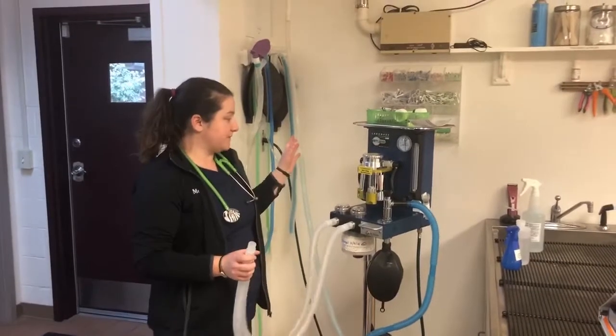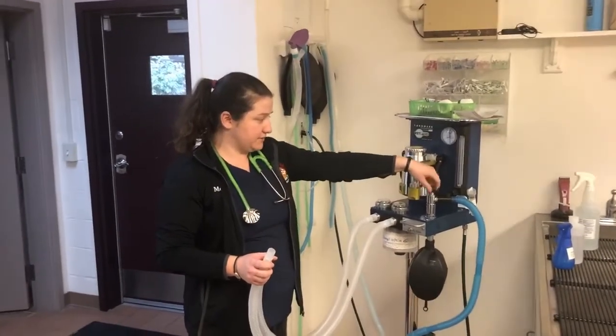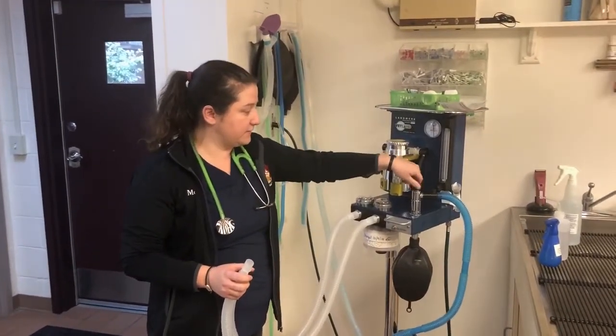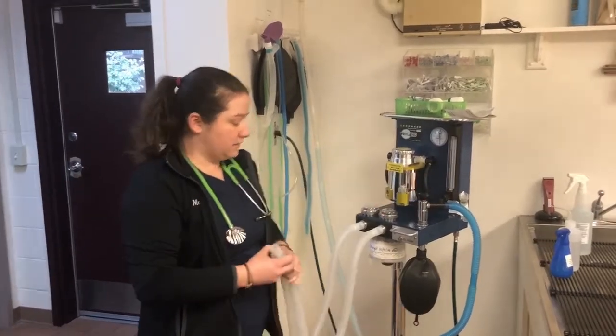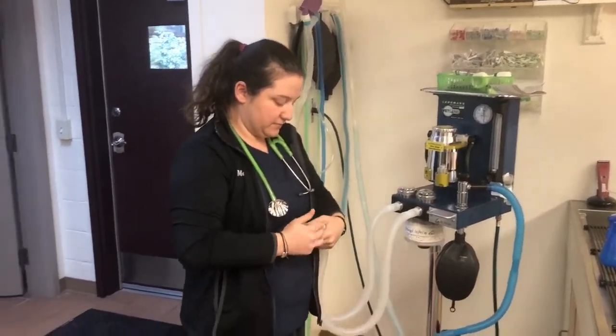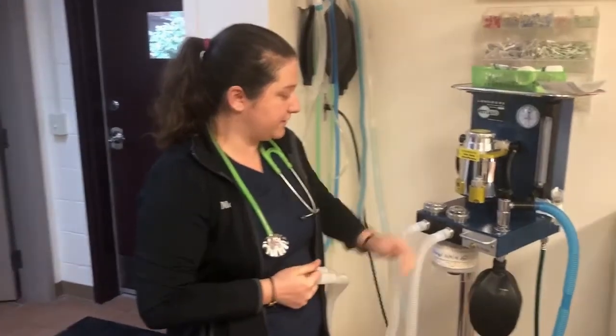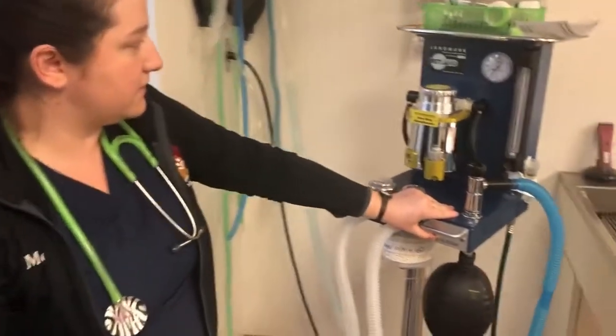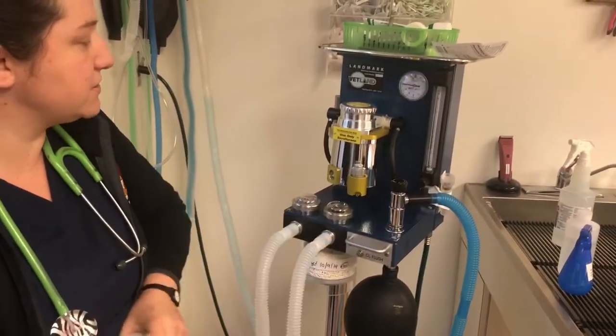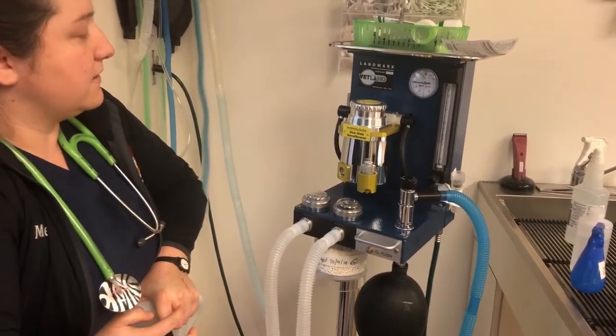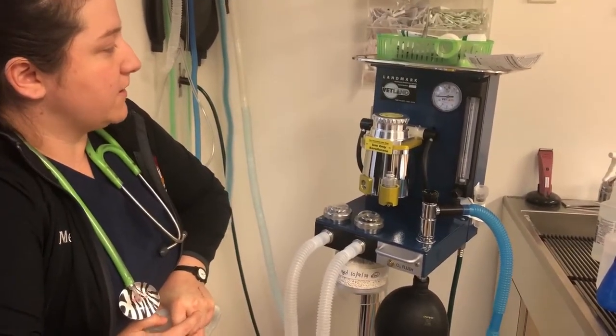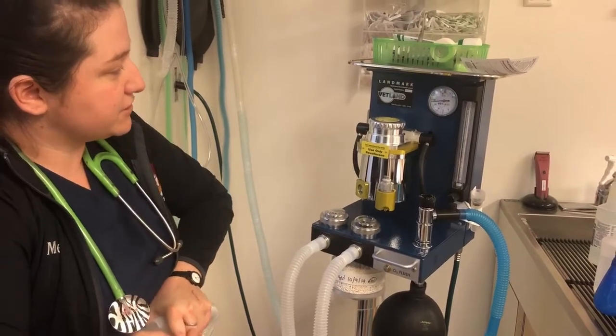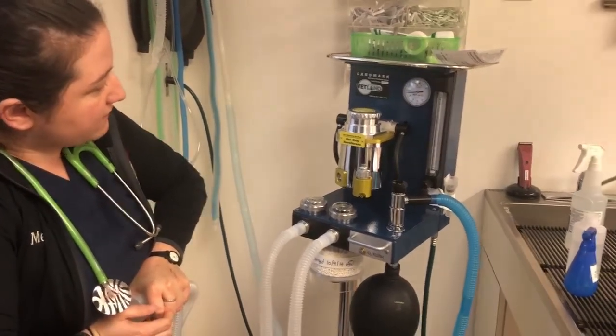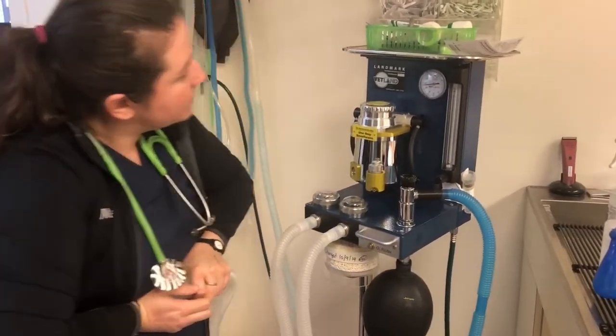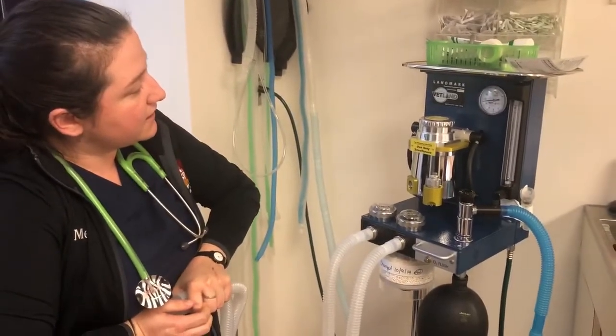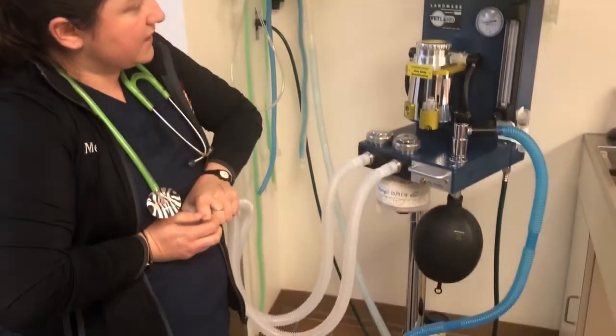So to leak test my anesthesia machine, first thing I'm going to do is shut off my pop-off valve. And then I'm just going to plug the end of my Y piece here and fill my reservoir bag with the O2 flush.